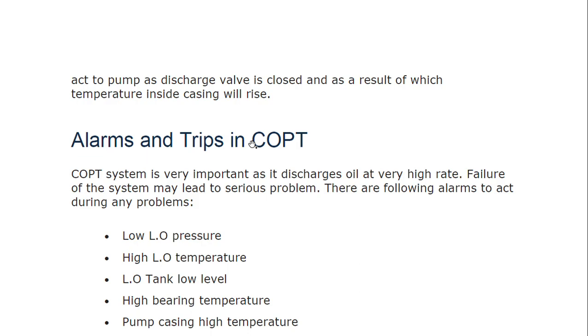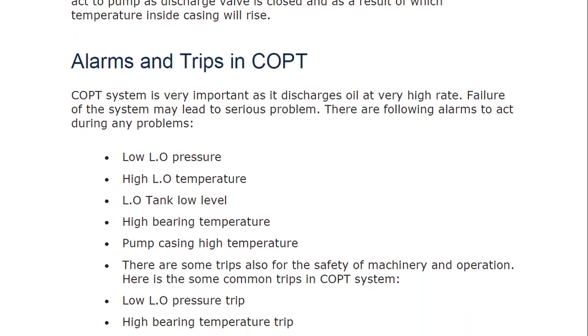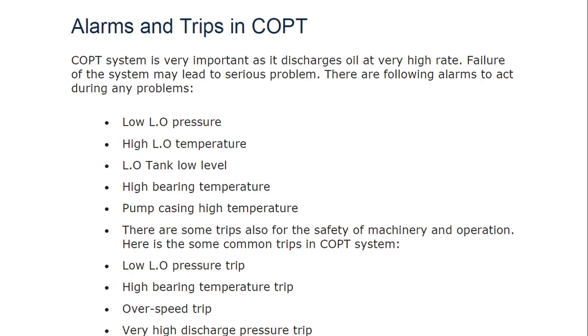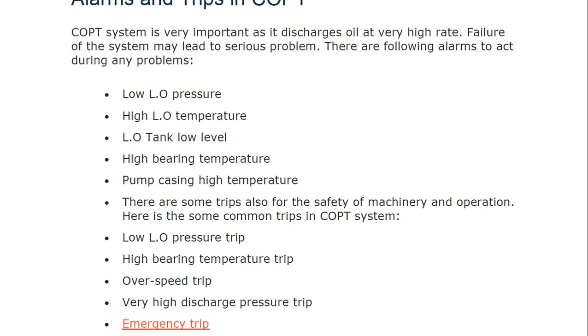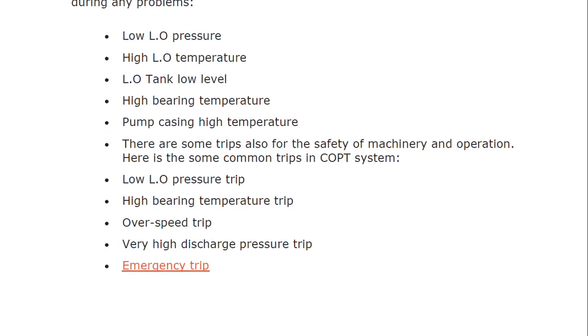Alarms and trips are also very important. A high rate of failure of the system may lead to serious problems. The alarms are: low lube oil pressure, high lube oil temperature, lube oil tank low level, high bearing temperature, and pump casing high temperature. The trips for safety are: low lube oil pressure trip, high bearing temperature trip, overspeed trip, very high discharge pressure trip, and emergency stop.